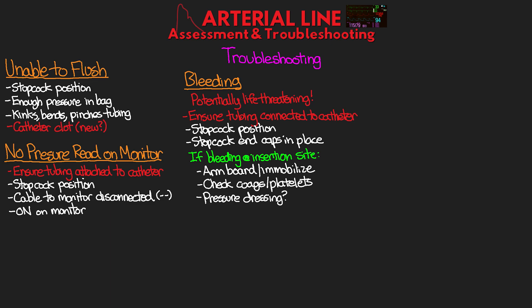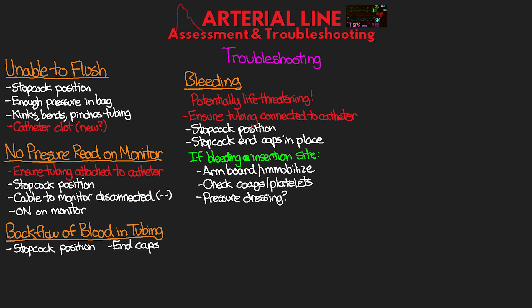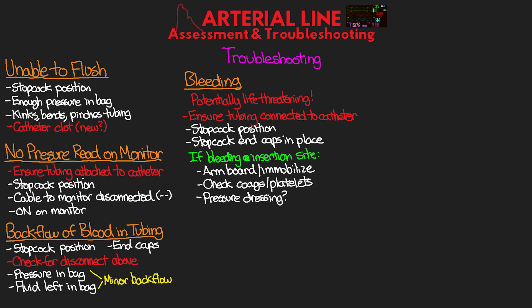Another issue is backflow of blood in the tubing. Check stopcocks and caps for proper positioning. If the stopcock is turned off to the transducer without a cap, this can lead to backflow and bleeding from the open port. Check for any disconnect in the system above where you notice the backflow. Also ensure you have enough pressure in the bag and sufficient fluid — if there's insufficient pressure or fluid to push forward, you'll start to see a blood backup in the line.